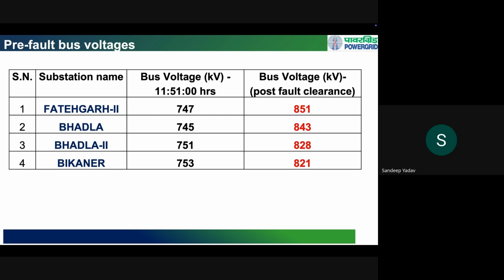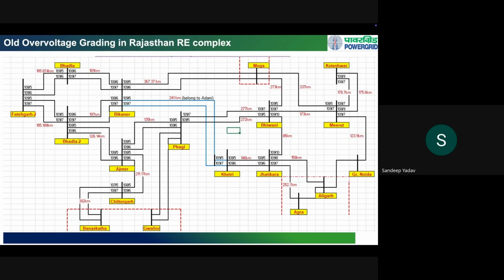So the rise in voltage, the step change in voltage, is very high in the case of weaker grids, because there is not enough system strength, or the short circuit ratio is very low. This is a slide which captures the grading of over voltage protection in the entire area. This was done previously. If you take a look at the pickup and time delays of the over voltage protection, they are in the same range. Circuit 1 is 108% and 5 seconds. Circuit 2 is 109% and 6 seconds. So this is the over voltage grading.